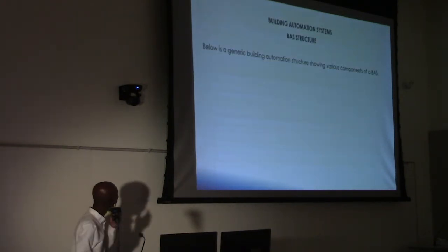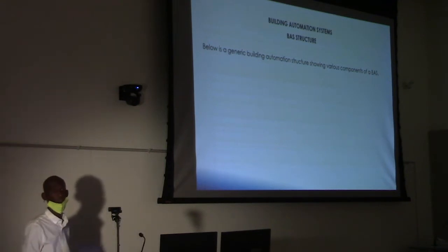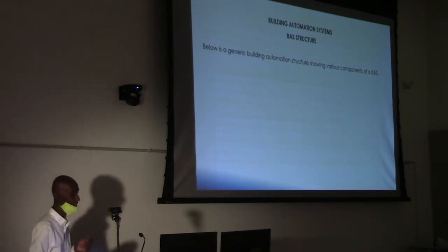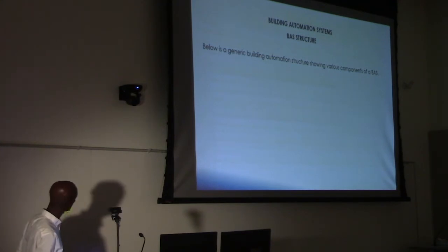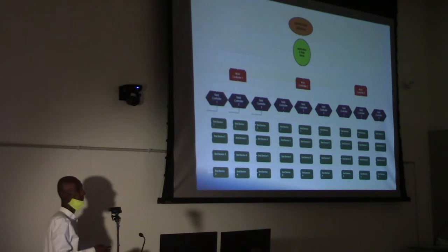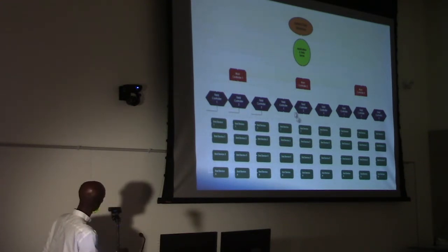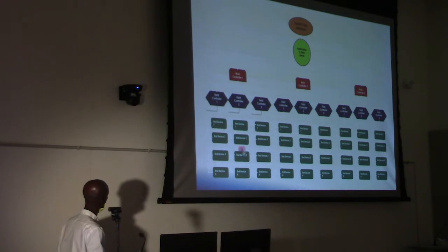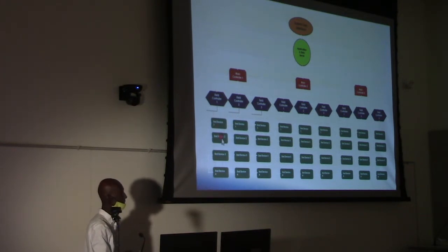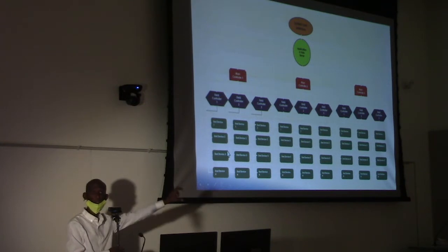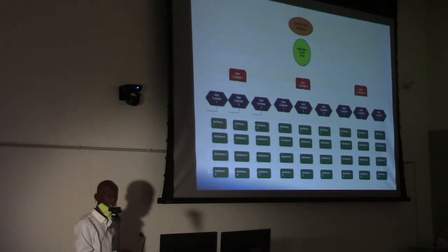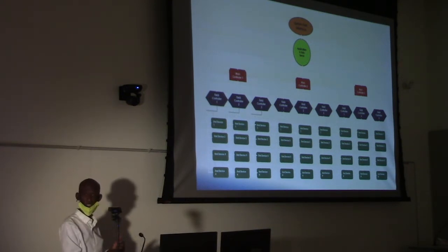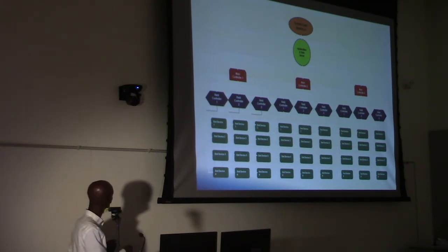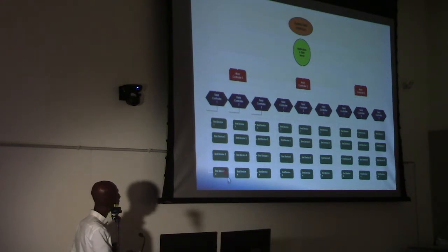So let's look a little bit at the components of a building automation system. I put together a small graphic, and I'll start from the bottom. So when you look at this here, I have N devices. N devices can be a temperature sensor, the monitor on the wall, can be a pressure sensor, can be a valve position, can be a damper position, can be a chilled water flow rate. So you have all those points, you call them points.